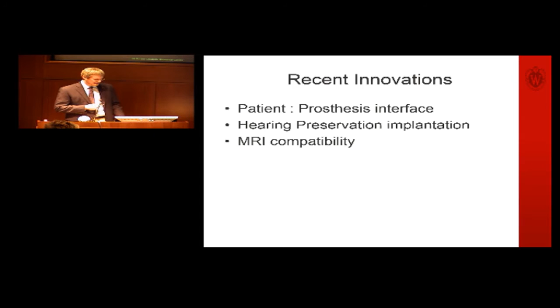So for the patient-prosthesis interface, one of the concepts that's gotten a lot of attention recently is trying to bring the electrode array, what is actually providing the stimulation to the nerve, and the nerve into close proximity. And there are some reasons this might be beneficial. There are some designs that I've shown here, both from Advanced Bionics and Cochlear Americas, which are the devices after all of the stylets have been removed. In other words, they're held straight, they're placed into the inner ear, and then a stylet of some type is removed, and then the device conforms to the shape of the snail shell.